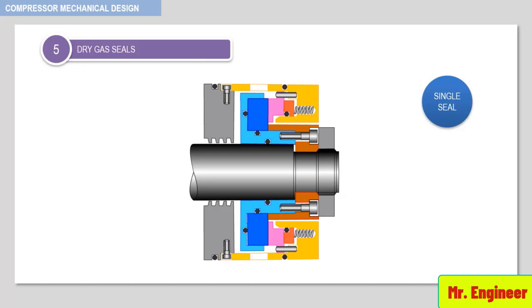Single seals are particularly advantageous as they occupy less space at the compressor ends and are best suited to keep the lateral critical speeds away. Carbon dioxide compressors used in fertilizers are a classical example where single seals are employed.